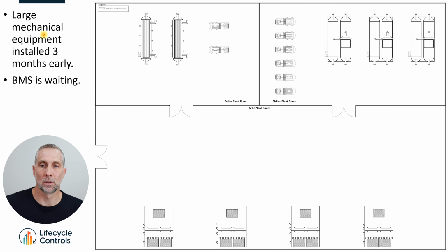So what normally happens, so here's a big plant room. On the top left, we've got 2 boilers and 2 boiler pumps. On the top right, we have a chiller plant room, 3 chillers, 3 chill water pumps, and 3 condenser water pumps. And this very large plant room at the bottom, the air handler unit plant room. I've got 1, 2, 3, 4 air handler units, and I'll zoom in on this later on, but basically this is the supply duct, the return and outside air ducts, some filters, heating and cooling coils, and a few doors on the side here. So this is a top view of a typical boiler cooling air handler unit plant room.